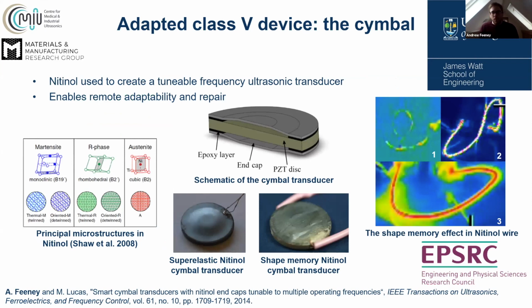Now, nitinol is an alloy of nickel and titanium, and it's a shape memory material. It exhibits two major microstructures with different physical properties and a third intermediate phase, which we call the R phase. The change in these microstructures, for example through modest changes in temperature, which can be very modest, in the order of only a few degrees Celsius, permits property changes in the material. One of these is elastic modulus, for example. Changing this elastic modulus causes a change in device resonance, and this is achievable in the order of thousands of hertz, which is ideal for an ultrasonic transducer if I want to make it adaptable.